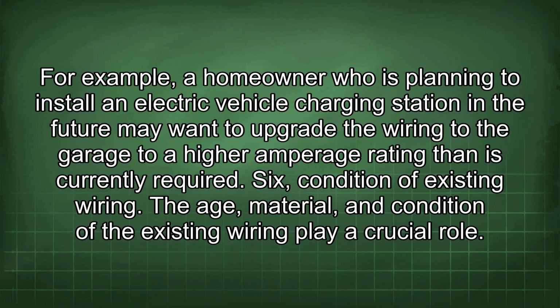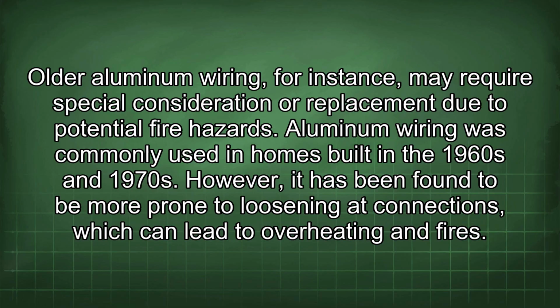6. Condition of existing wiring. The age, material, and condition of the existing wiring play a crucial role. Older aluminum wiring, for instance, may require special consideration or replacement due to potential fire hazards. Aluminum wiring was commonly used in homes built in the 1960s and 1970s. However, it has been found to be more prone to loosening at connections, which can lead to overheating and fires.